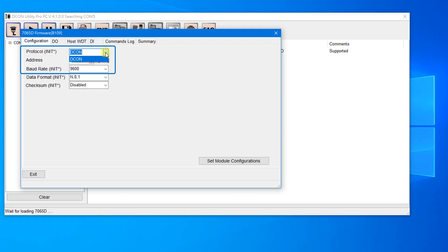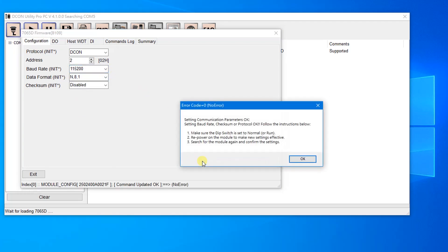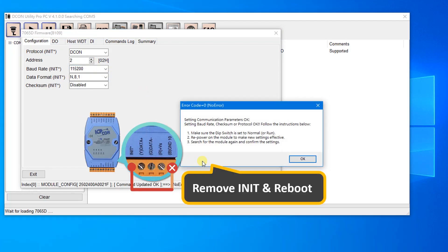The I7000 series module only supports the DCON protocol. In this case, set the address to 2 and the baud rate to 115200. Then click the button — the dialog box will prompt you to remove the init wiring and reboot the module. Click OK.